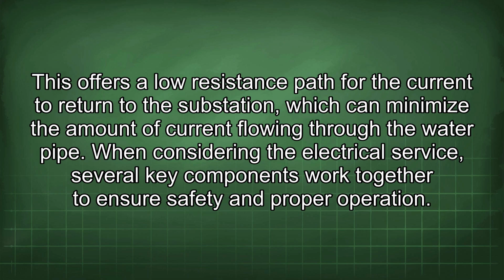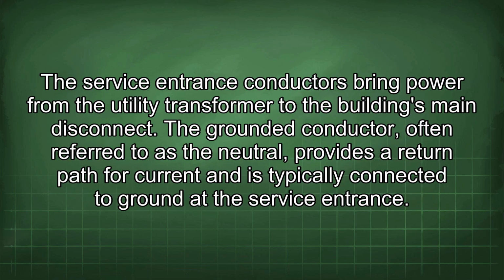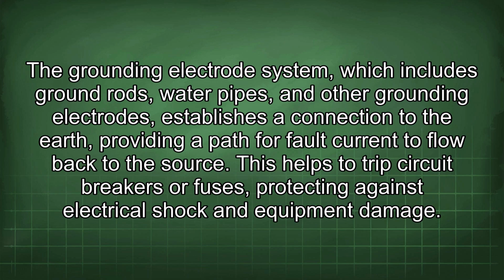When considering the electrical service, several key components work together to ensure safety and proper operation. The service entrance conductors bring power from the utility transformer to the building's main disconnect. The grounded conductor, often referred to as the neutral, provides a return path for current and is typically connected to ground at the service entrance. The grounding electrode system, which includes ground rods, water pipes, and other grounding electrodes, establishes a connection to the earth, providing a path for fault current to flow back to the source. This helps to trip circuit breakers or fuses, protecting against electrical shock and equipment damage.